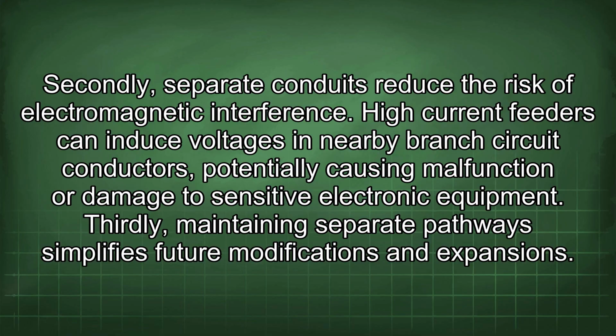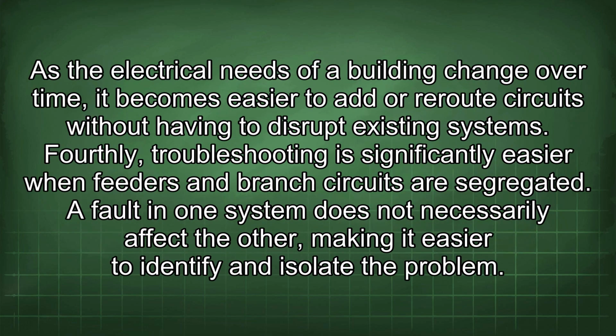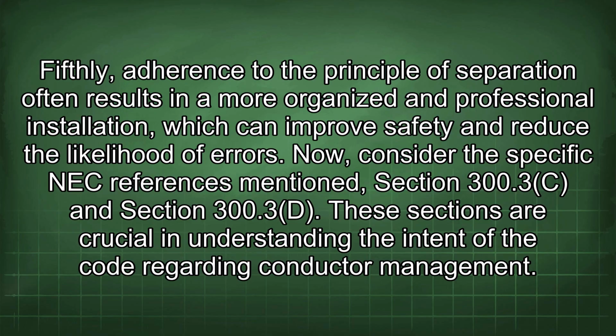Thirdly, maintaining separate pathways simplifies future modifications and expansions. As the electrical needs of a building change over time, it becomes easier to add or reroute circuits without having to disrupt existing systems. Fourthly, troubleshooting is significantly easier when feeders and branch circuits are segregated. A fault in one system does not necessarily affect the other, making it easier to identify and isolate the problem. Fifthly, adherence to the principle of separation often results in a more organized and professional installation, which can improve safety and reduce the likelihood of errors.